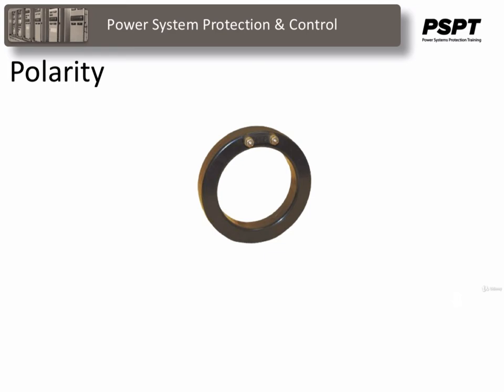Designating the polarity of a CT is very important, and it's usually done by the manufacturer to indicate the polarity of the secondary with respect to the polarity of the primary. The primaries and secondaries are marked to indicate which direction the current will flow during each half cycle of current. In this case, we've got a spot on the facing side of the CT, and we have a spot on the right-hand terminal of the secondary of that CT in this picture.